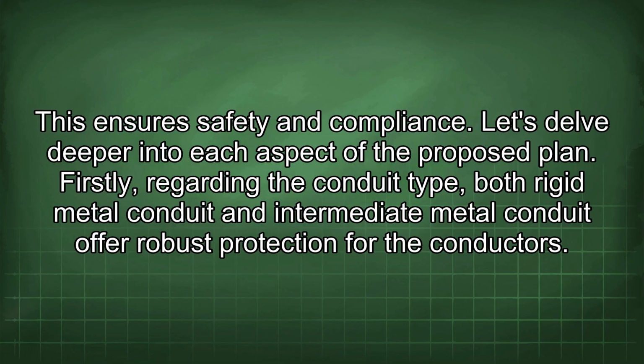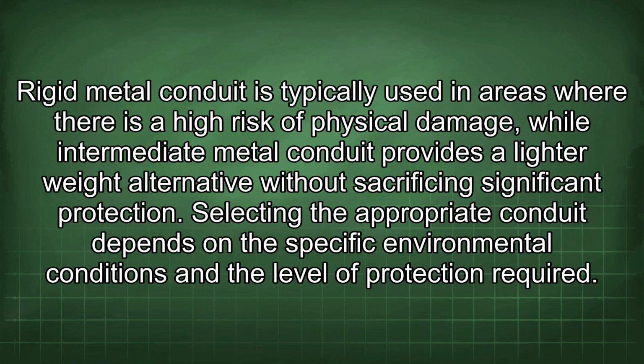Firstly, regarding the conduit type, both rigid metal conduit and intermediate metal conduit offer robust protection for the conductors. Rigid metal conduit is typically used in areas where there is a high risk of physical damage, while intermediate metal conduit provides a lighter weight alternative without sacrificing significant protection. Selecting the appropriate conduit depends on the specific environmental conditions and the level of protection required.